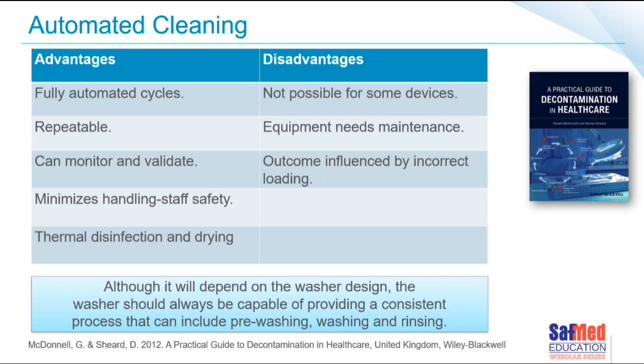The equipment itself will need some form of maintenance, and cleaning efficacy can be affected by how we load our washer disinfectors — incorrect loading can affect the outcome. The advantages, however, certainly outweigh the disadvantages. Cycles are fully automated and repeatable — the machine will take in the right amount of water, the right temperature, the right amount of detergent, dose the chemistry at the right time, and wash with the same force of water every single time.